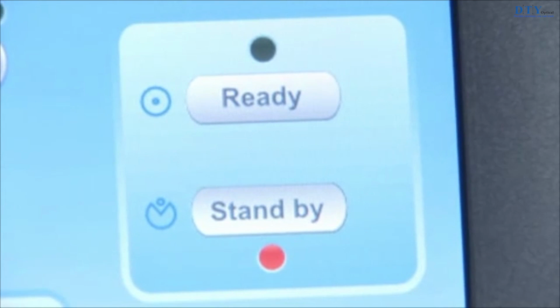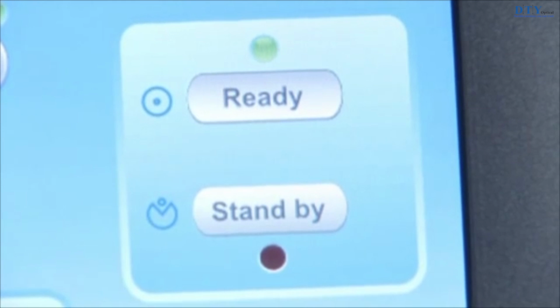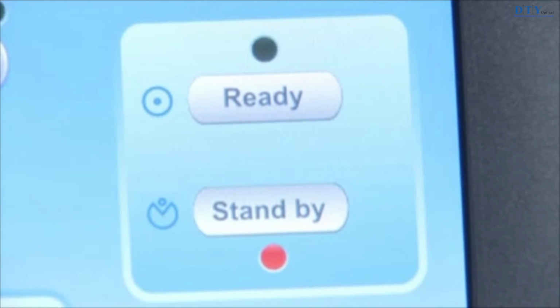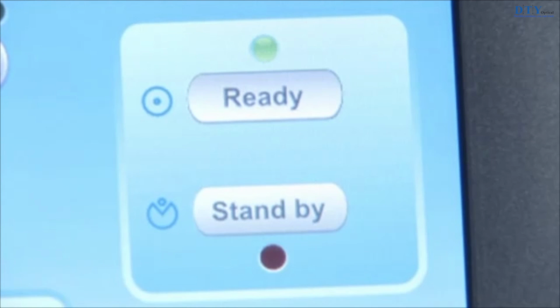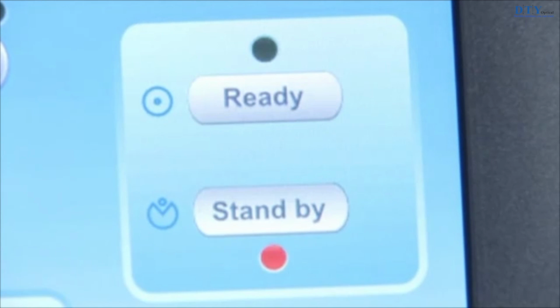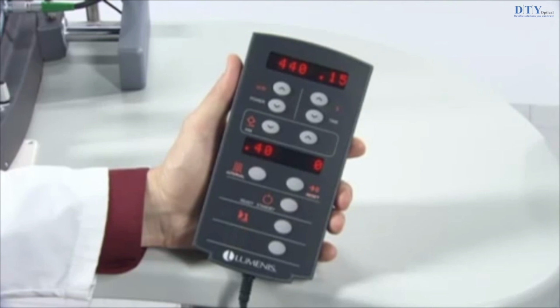To select the laser mode from the control screen, press the Ready button for ready mode or press the Standby button for standby mode. The laser automatically switches from ready mode to standby mode if it remains idle for more than 5 minutes. To select the laser mode from the remote control, press the Ready/Standby selector to toggle between ready and standby modes. The icon for the selected laser mode illuminates.